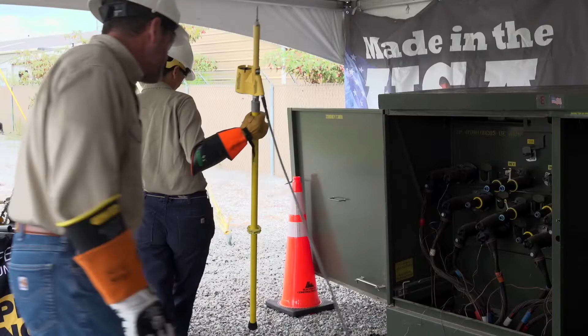And what we did is we went phase to ground. So when you're phasing, you're always gonna verify that you have power, obviously. You're also gonna verify the tool is functioning properly on a live known voltage source. The capacitive test point, that's fine, it's live. All right, so that satisfies that.